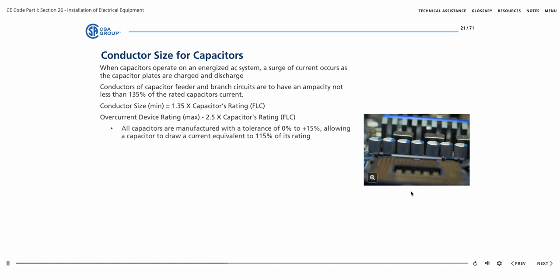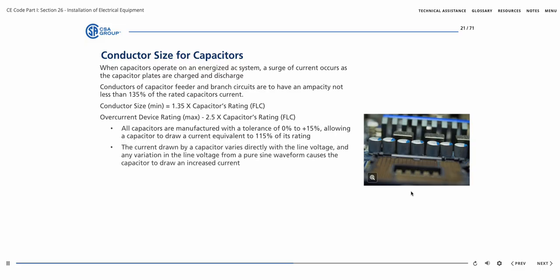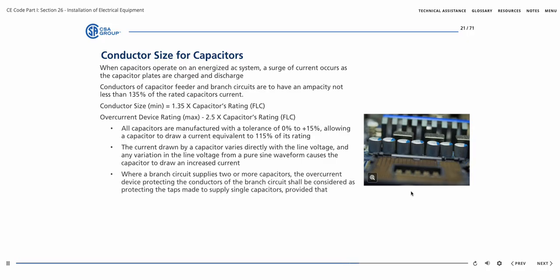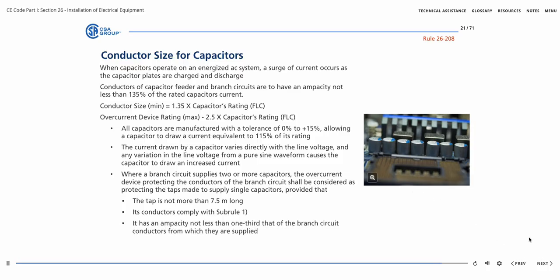It is helpful to first know that all capacitors are manufactured with a tolerance of 0% to plus 15%, allowing a capacitor to draw a current equivalent to 115% of its rating. In addition, the current drawn by a capacitor varies directly with the line voltage, and any variation in the line voltage from a pure sine waveform causes the capacitor to draw an increased current. Where a branch circuit supplies two or more capacitors, the overcurrent device protecting the conductors of the branch circuit shall be considered as protecting the taps made to supply single capacitors, provided that the tap is not more than 7.5 meters long and its conductors comply with Sub-Rule 1 and have an ampacity not less than 1/3 that of the branch circuit conductors from which they are supplied.